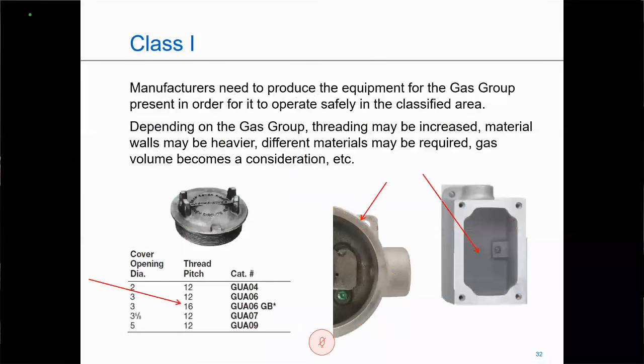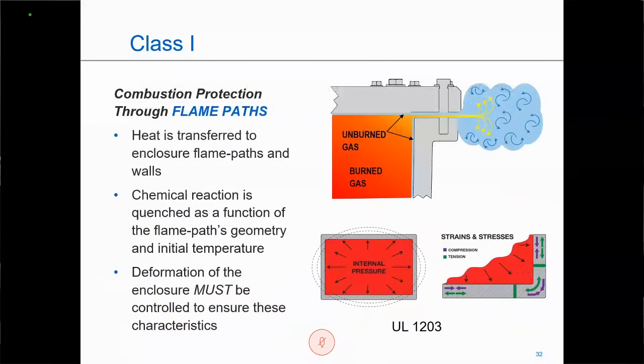So sometimes when manufacturers are determining and looking for approval for a particular gas group, they may change thread pitching for the particular product. You may have material walls thicker. There could be volume of gas concerns within the particular unit. So there's different aspects that a manufacturer looks at when they're looking to have a particular product approved for a particular gas group.